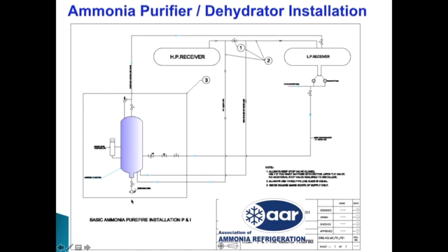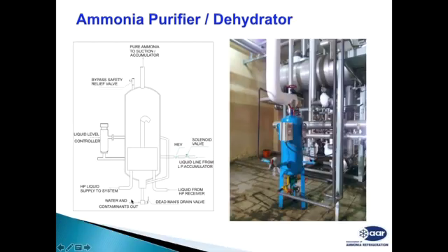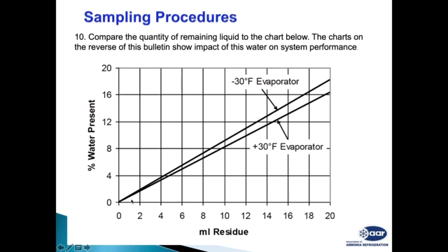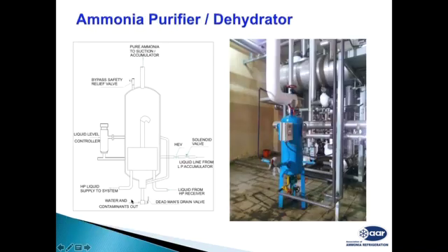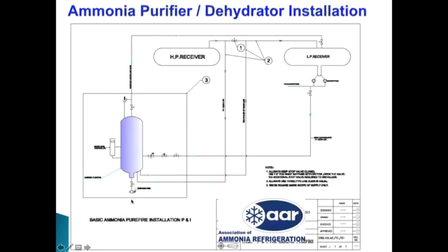If you are not using that ammonia dehydrator, then you have to drain it from the oil drain points provided at the low pressure vessel and also at your evaporator sites, low pressure sites. But remember, when you are using these points, there is also a possibility of ammonia coming out from that point. And as water is mixed into the ammonia, it may not separate out and it may not evaporate completely. So you need to take proper precautions when you are draining it manually. It is better to use a dehydrator which will separate ammonia and water and give you only water to be drained out.